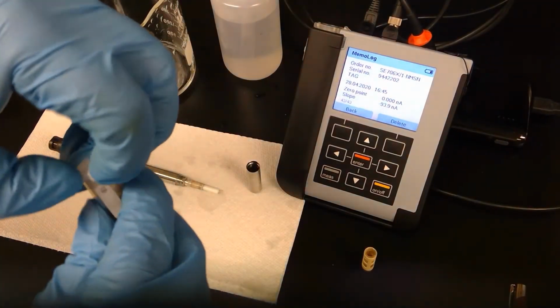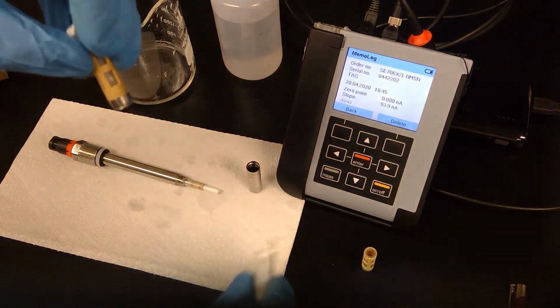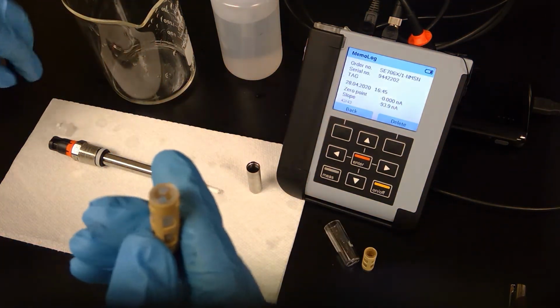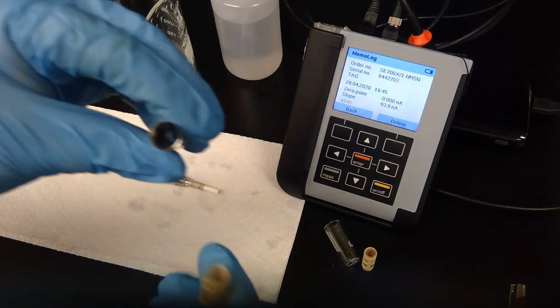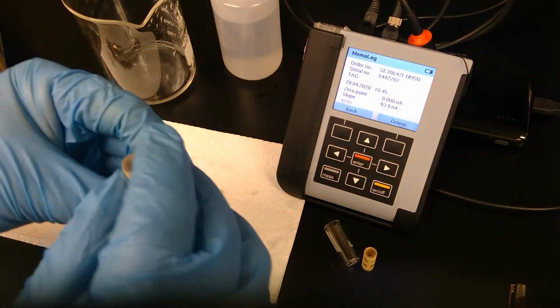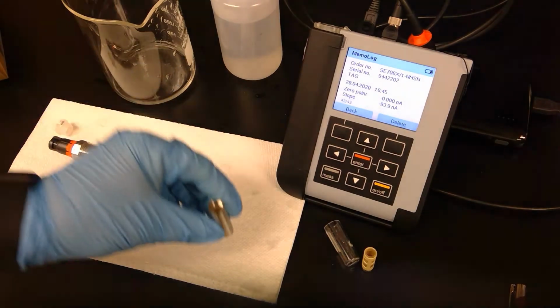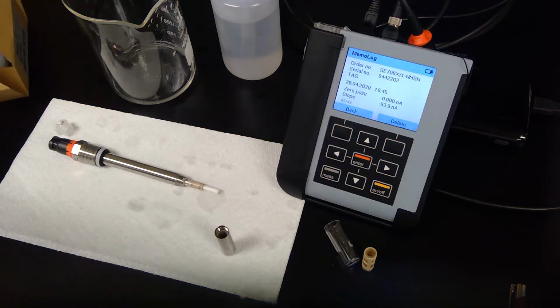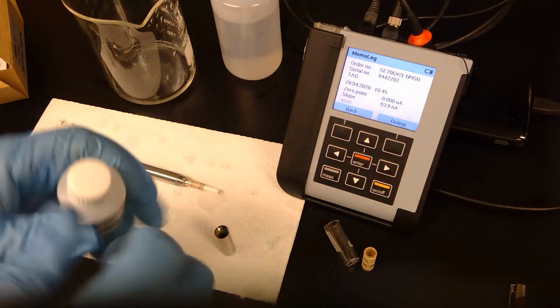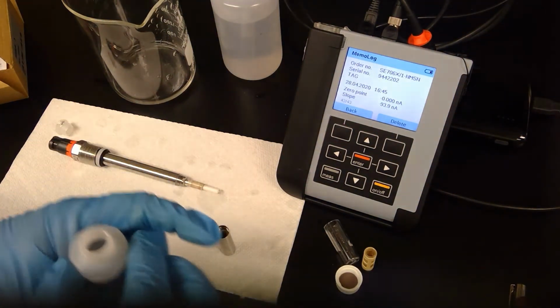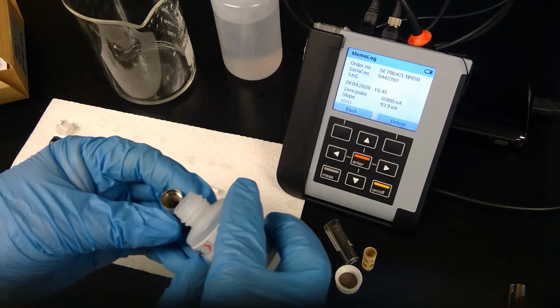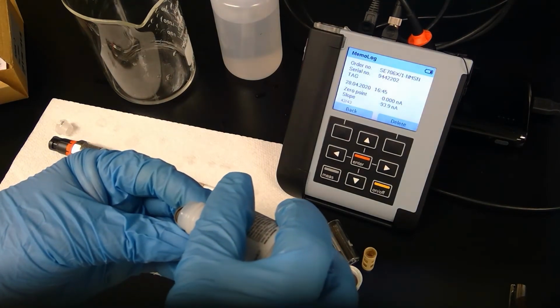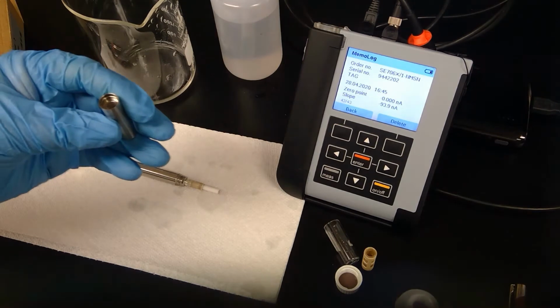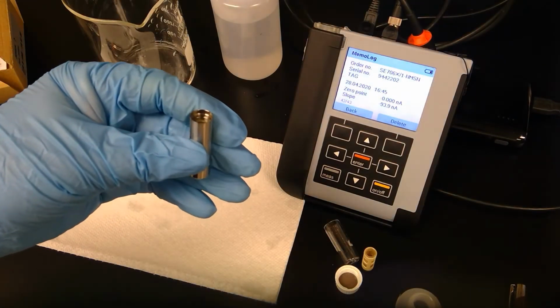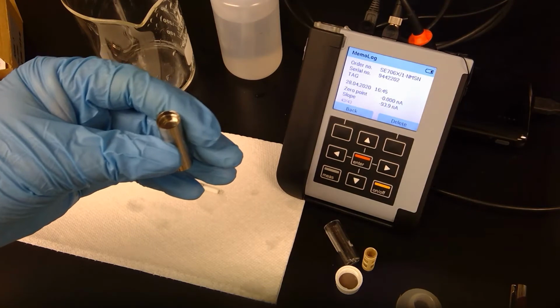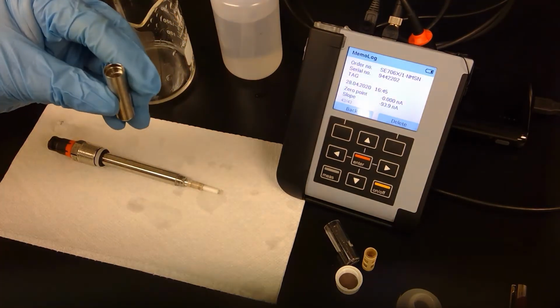So now we're going to take the new membrane out of its little container. Okay. All you do is take the sleeve and drop the new membrane into it, and then take the bottle of electrolyte, the O2 electrolyte, out of the kit, and fill to the top of the membrane, not the cap, but the sleeve, just to the top of the membrane. I'll put a little bit more than I needed to, but that's okay. You can't put too much in here, but you definitely can not put enough and cause a problem.